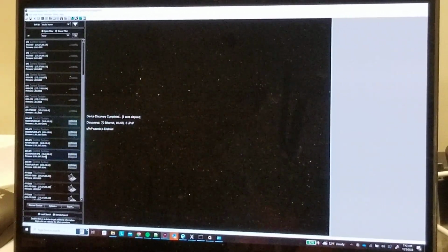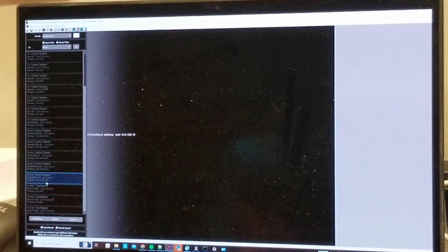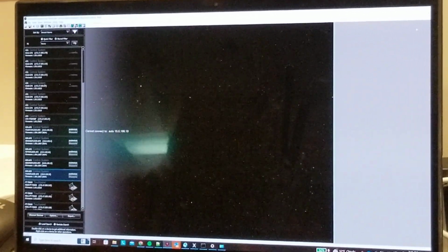So I'm curious if this will allow me to talk to it this time. If I go to 3rd floor, hit connect to address. One thing I'm noticing though is the DALIs didn't populate again. It's all the same parts as last time. Interesting. So those are Ethernet back to the processor. Okay. And the one bit of good news here is that everything seems to be communicating over the Ethernet, just not back to me right now, to this laptop. Okay. Which I'm trying to troubleshoot, but I don't know.